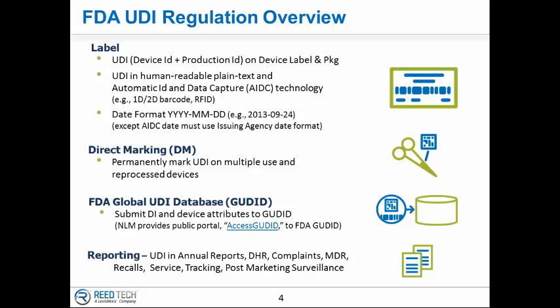And then after that 30 days, the product automatically closes the period, and then it's fully published, and most importantly, made available on the AccessGUDID to the public. So during that grace period, the FDA expects the holder of that data to make sure, especially those 11 fields that are all of a sudden going to be fixed at the end of that 30 days, to go in and verify those records, those values. So hopefully that answers the question about the published date.